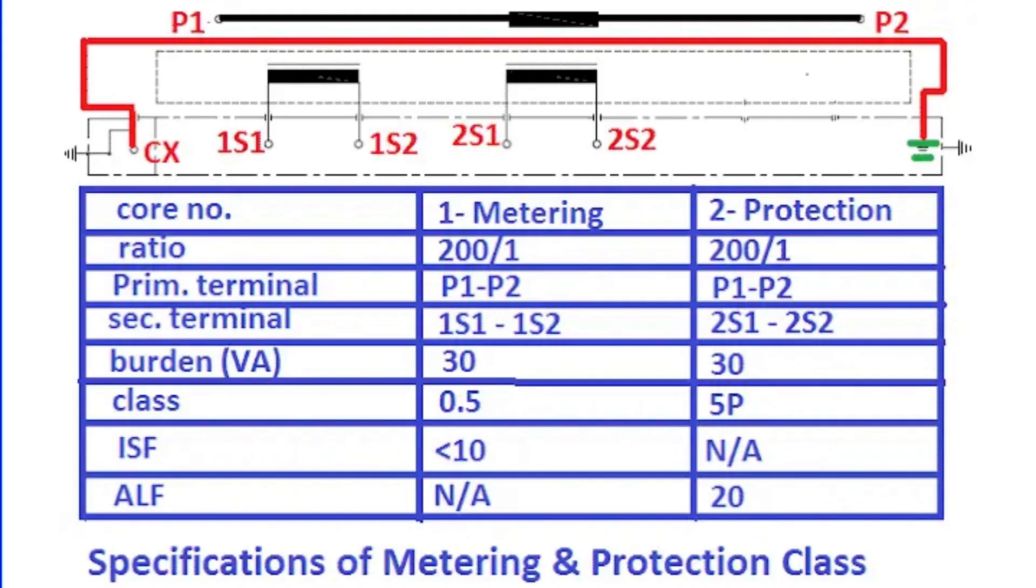For instance, if the ISF is 3, the CT core saturates when the primary current exceeds 3 times the rated current, limiting the secondary current to safeguard the connected meters.